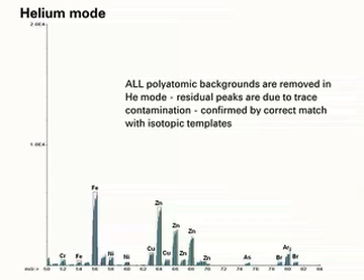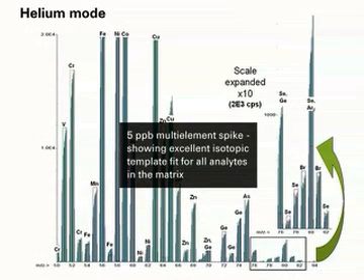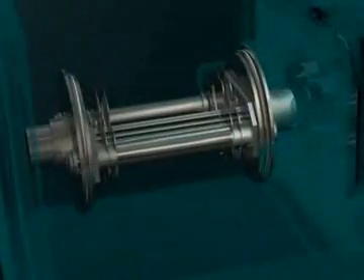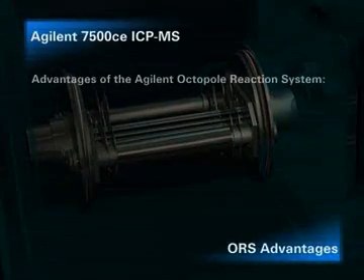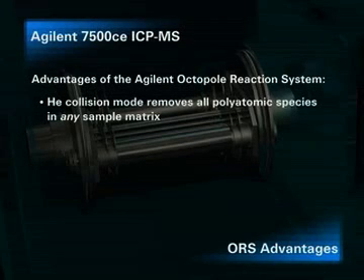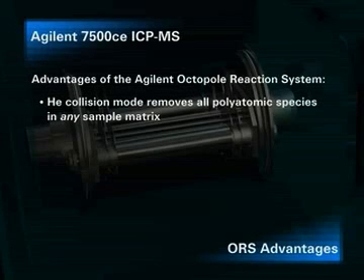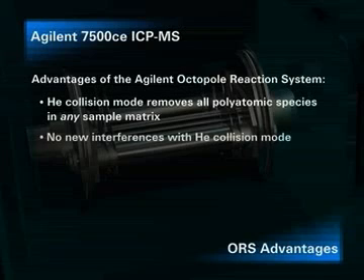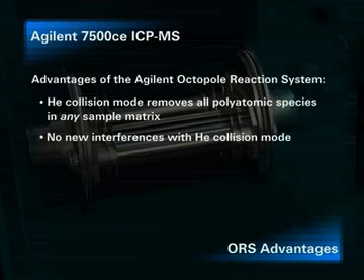Helium mode has removed all polyatomic interferences simultaneously. Adding a 5 parts per billion multi-element spike confirms all analytes are easily measured in this very complex sample matrix. The octopole reaction system offers the analyst a number of advantages. Its unique helium collision mode removes all polyatomic species simultaneously, and no prior knowledge of the sample matrix is required. Unlike reactive cell gases, pure helium cell gas is inert and does not react with the analyte or sample matrix. Reactive gases are not suitable for multi-element analysis in complex sample matrices, since they react with the sample matrix forming new interferences in the cell, which can bias analytical data.